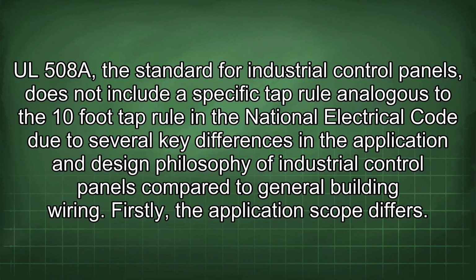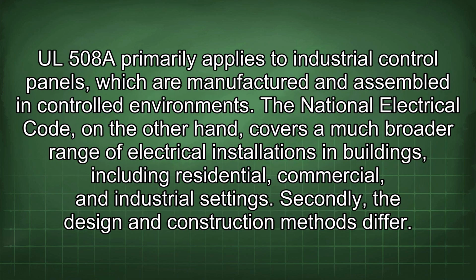devices. UL 508A, the standard for industrial control panels, does not include a specific tap rule analogous to the 10-foot tap rule in the National Electrical Code due to several key differences in the application and design philosophy of industrial control panels compared to general building wiring. Firstly, the application scope differs. UL 508A primarily applies to industrial control panels, which are manufactured and assembled in controlled environments. The National Electrical Code, on the other hand, covers a much broader range of electrical installations in buildings, including residential, commercial, and industrial settings. Secondly, the design and construction methods differ.